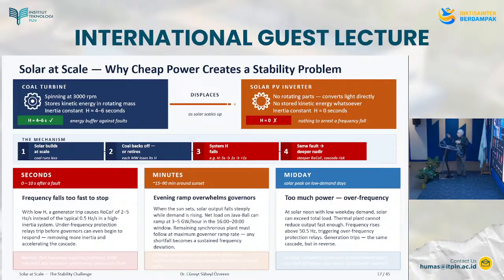So the frequency falls because you lost a generator, and then you lose another generator because the frequency protection operates. You lose another generator. That means even less in the system, less inertia. So the frequency trip of the remaining generators will work. They'll come out. The generators are trying to protect themselves from the fall of frequency. So once they sense a steep drop, they'll just come out, which will make the problem worse.